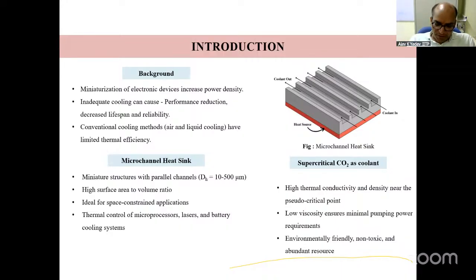Now, most cases people use water in microchannels. But considering Reynolds number, rho V d by mu - the diameter d is very small and mu is fixed for water, so it is very difficult to achieve turbulent flow in a microchannel. To achieve a realistic turbulent velocity you would need very high water velocity, which creates a very high pressure drop - essentially unrealistic. So with water, to remove heat in large amounts you need turbulent flow, but turbulent flow with water is very difficult to achieve in microchannels.